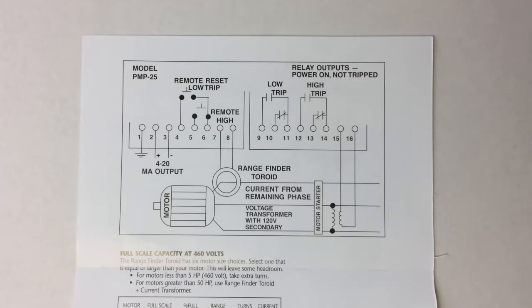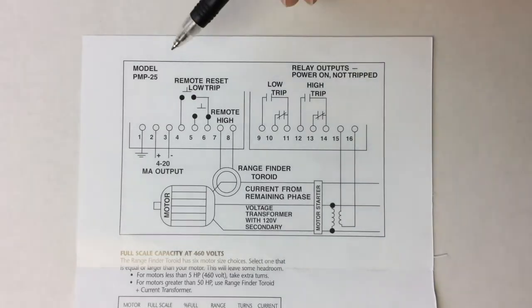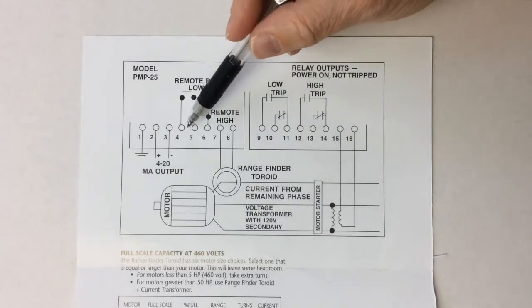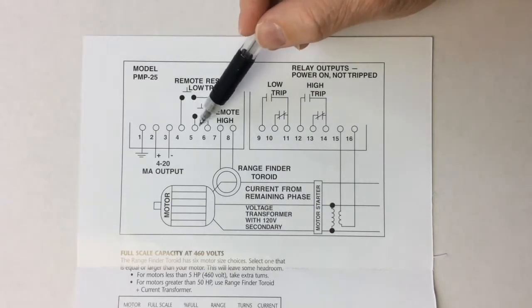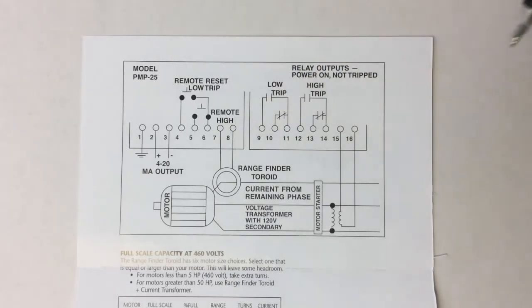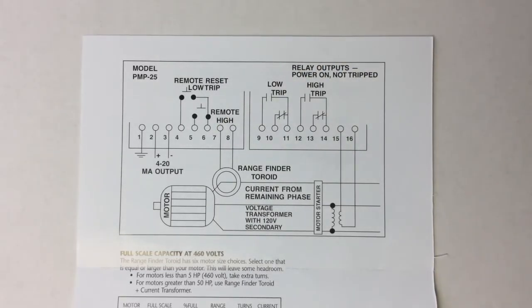Once tripped, the output relays will latch. They can be reset manually by the front panel reset button or by a remote switch connected to the terminal strip. The remote resets can also be hardwired together for automatic reset. Reset can only be done if the trip condition no longer exists or if the motor is off.